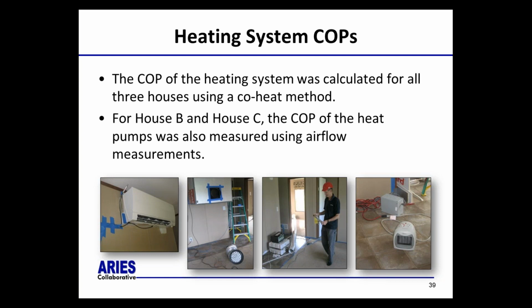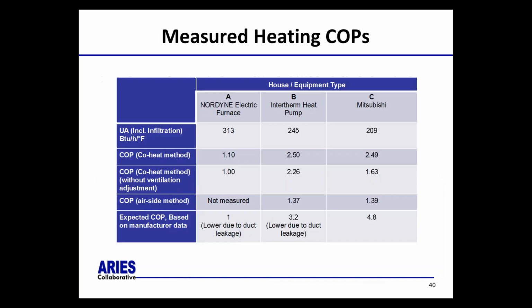So we measured the COP in these two methods, and we did that for all the houses. We found that the COP for the electric furnace was a little more than 1, so about what we expect, one for electric resistance heating. For the House B heat pump, about 2.5, and for the mini split heat pump, we also came up with about 2.5, which was a bit surprising. We were expecting something in the order of 4 or even higher for that heat pump. Those were using the co-heat method.